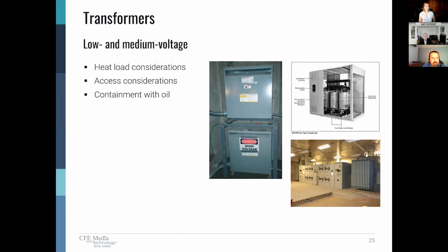Now, there are all types of oils out there. Mostly we've moved to safe type oils, but the local authority having jurisdiction may require a small bathtub to be constructed for oil spill containment, so that you make sure the oil doesn't go down some floor drain. The thing about transformers is this is where your HVAC guy and even your structural come in. You're going to have to talk to them, particularly on the large medium voltage type transformers. They're the ones that put off the heat in the room. HVAC engineers want to know how many BTUs it's putting out.